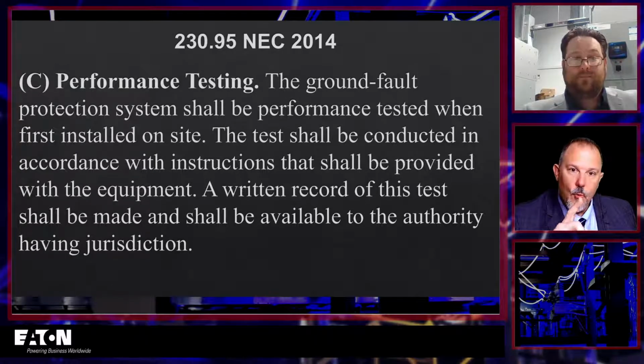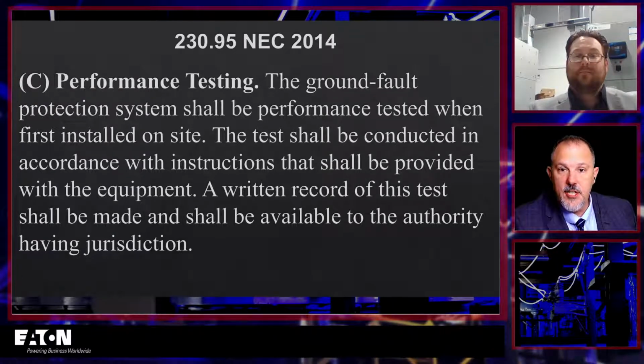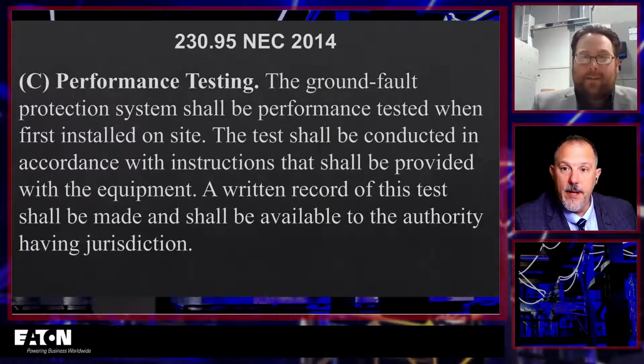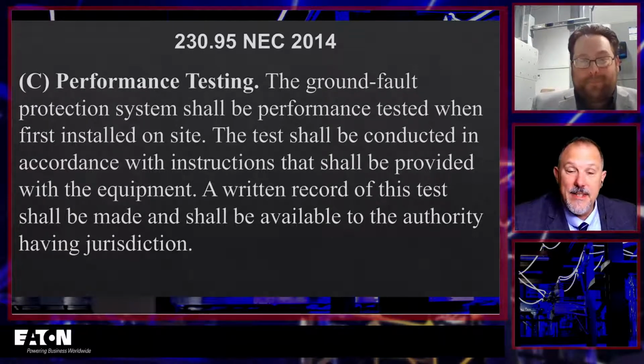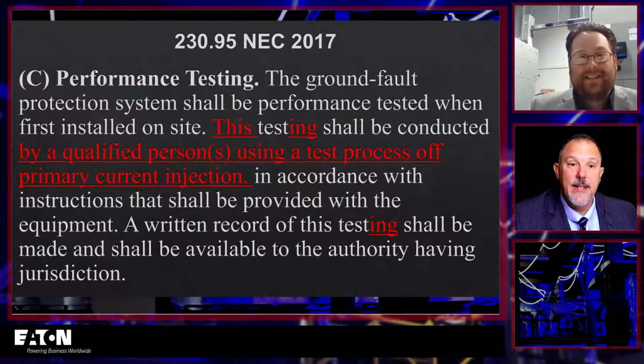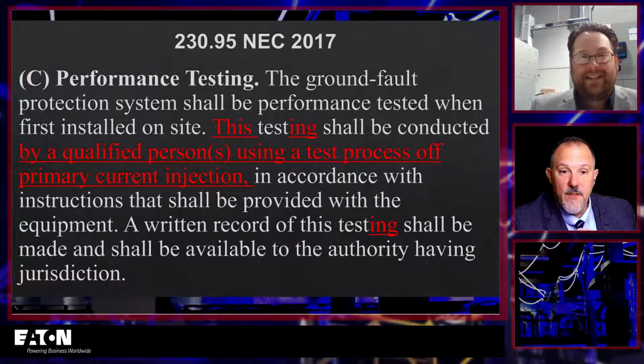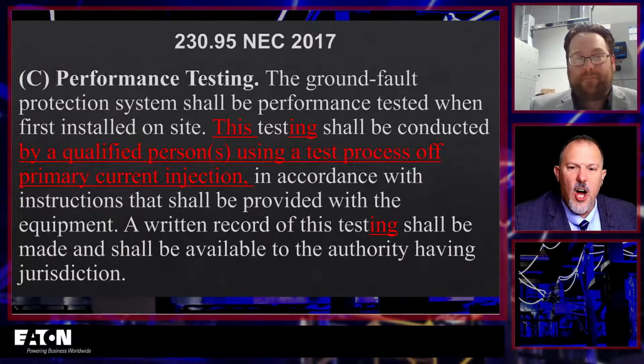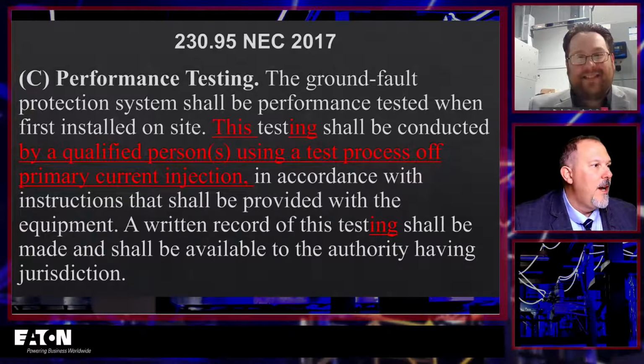So what is often missed, and we've lived with this performance testing for years, is that testing shall be conducted in accordance with instructions provided with the equipment, right? And then in the 2017 code, it said that you have to be a qualified person and use a test process, not off of, geez, I can't spell.